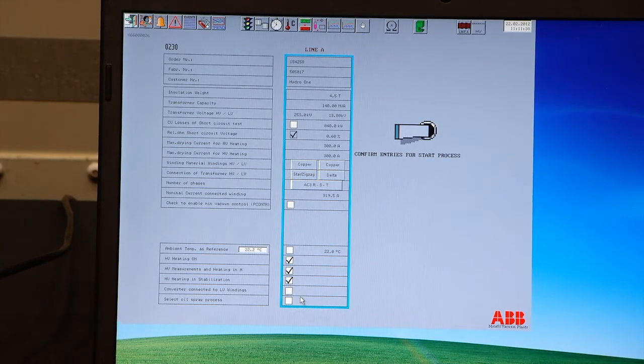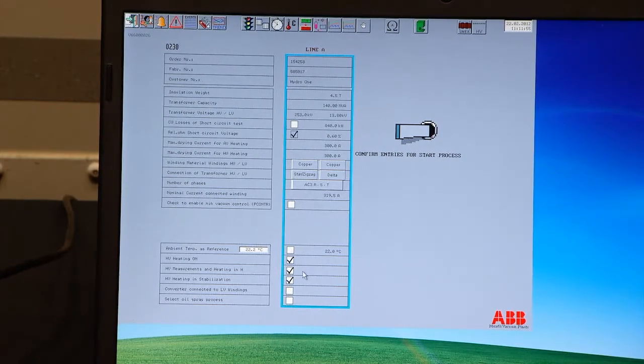Yeah, because here we have a nominal current of 3000 amps, I think, on the low voltage, and we can supply 500, 600 amps. So it's a fraction of that. If you have a very small voltage difference between the high and low voltage side, and you know that you have a high current density on the high voltage side, so that one will heat extremely much faster than the low voltage.